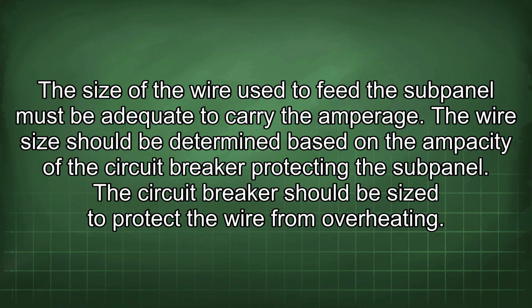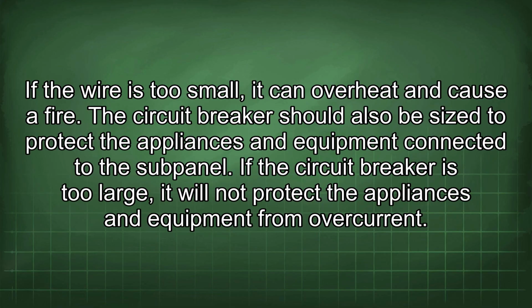The wire size should be determined based on the ampacity of the circuit breaker protecting the subpanel. The circuit breaker should be sized to protect the wire from overheating. If the wire is too small, it can overheat and cause a fire. The circuit breaker should also be sized to protect the appliances and equipment connected to the subpanel. If the circuit breaker is too large, it will not protect the appliances and equipment from overcurrent.